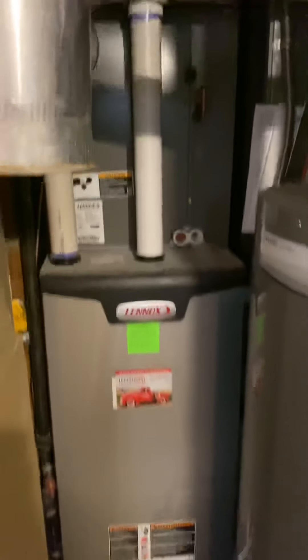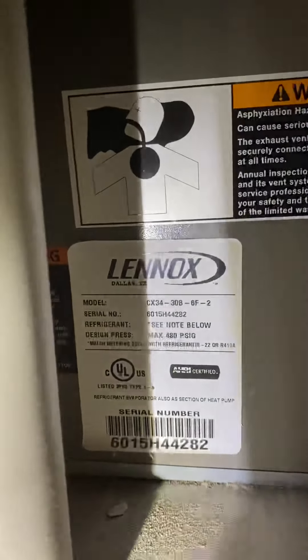Inside, here's the furnace and AC coil. The TXV is already in there. For the drain, we'll tie into the existing three-quarter inch drain pipe right there — 10 feet of PVC with a standard easy trap.